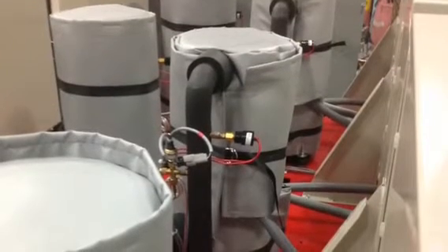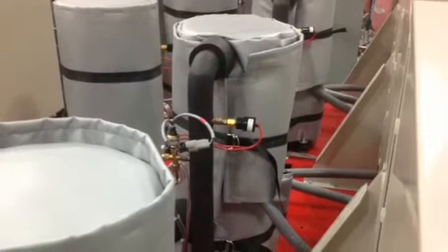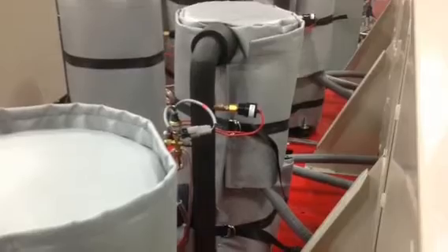through the gray seal-tight. In this top-down view, each module shows 3 seal-tight, 1 for power in and 2 for each compressor. This video clip pans around to the right to follow the seal-tight, which comes from the opposite end single point power junction box up through the red frame and into the underside of the individual module power junction box.